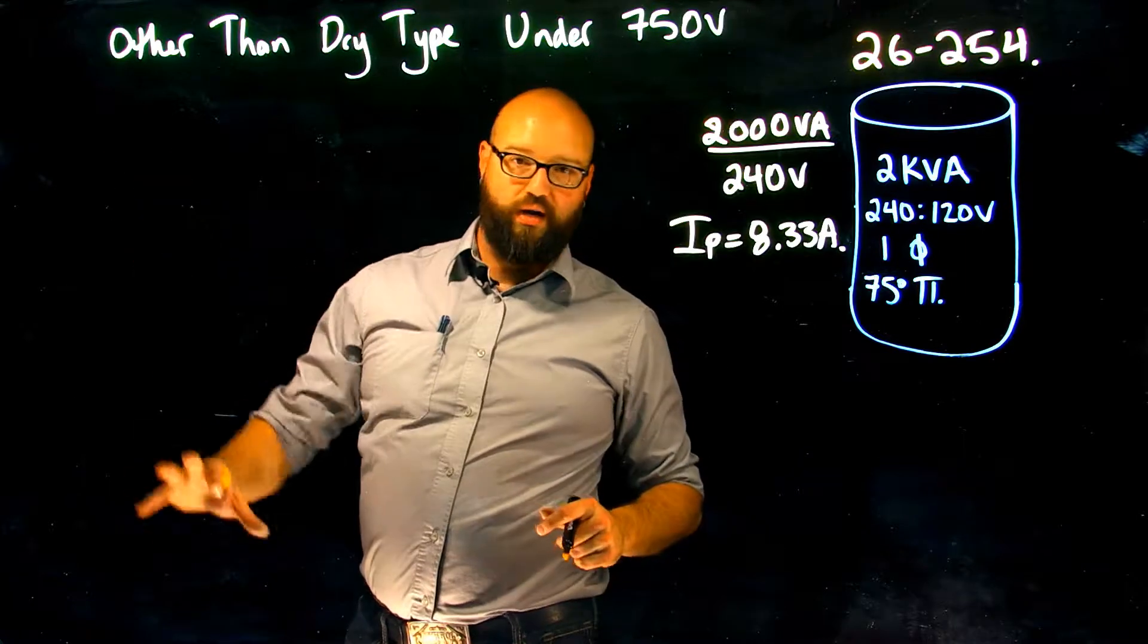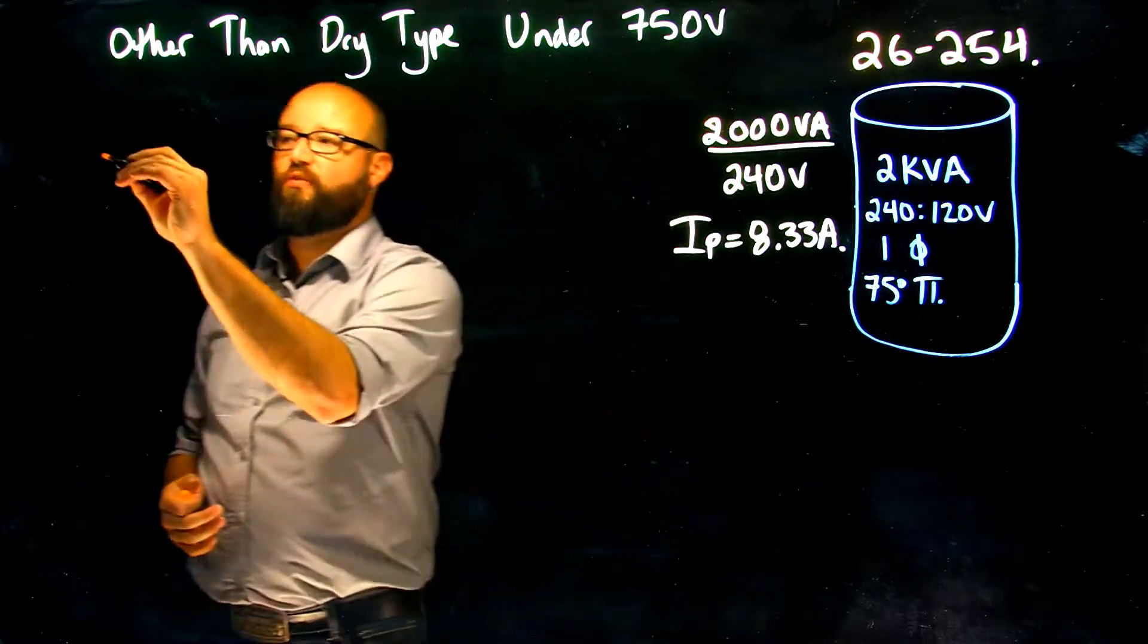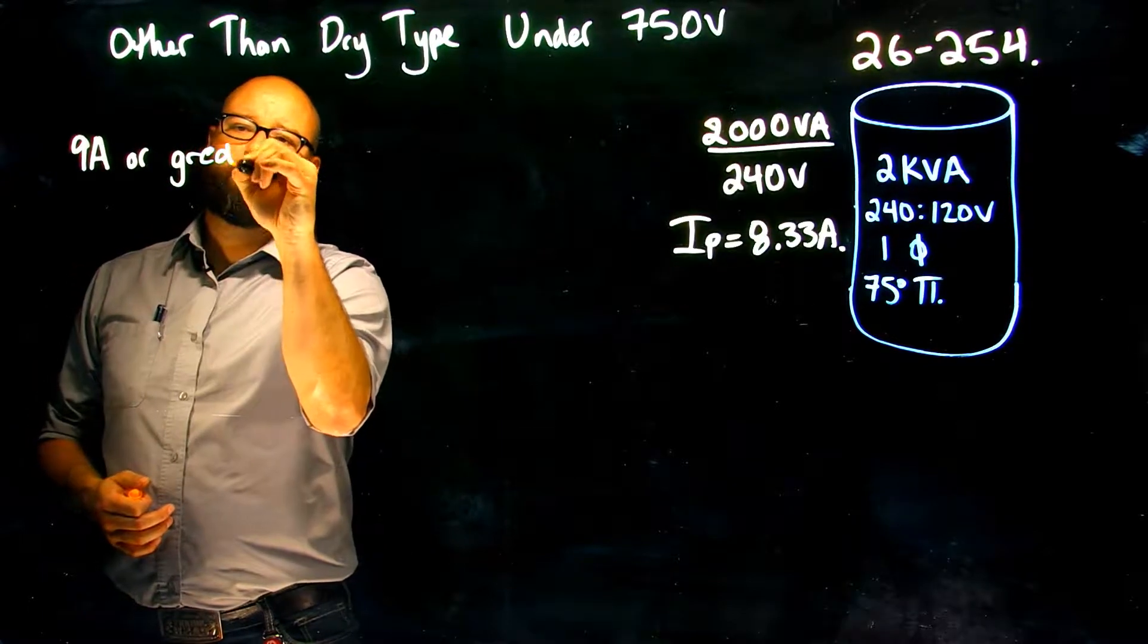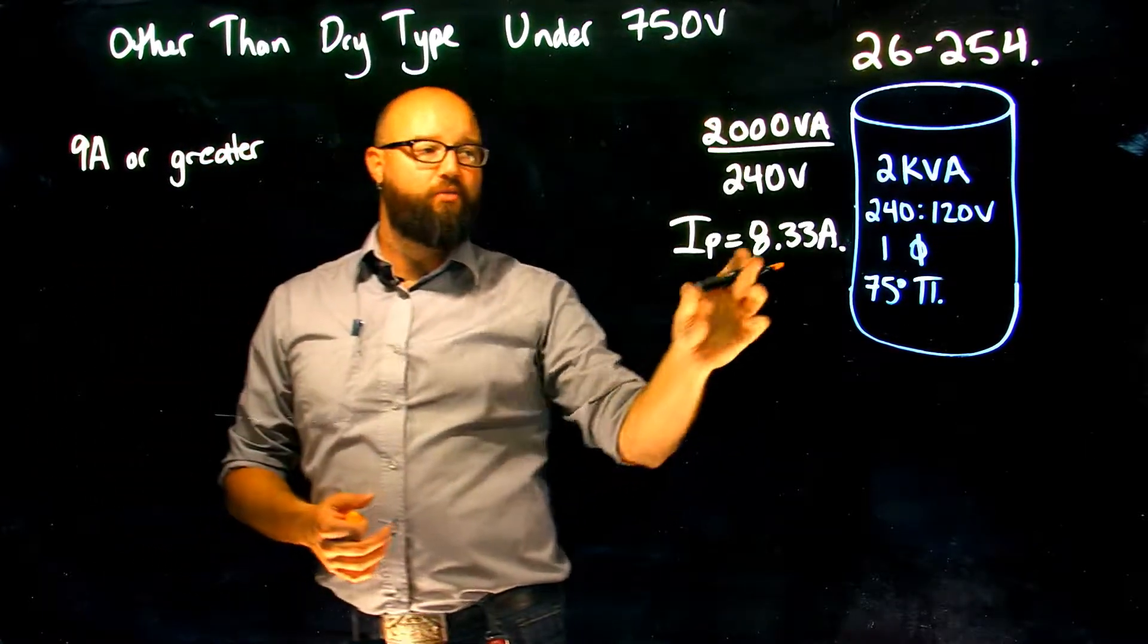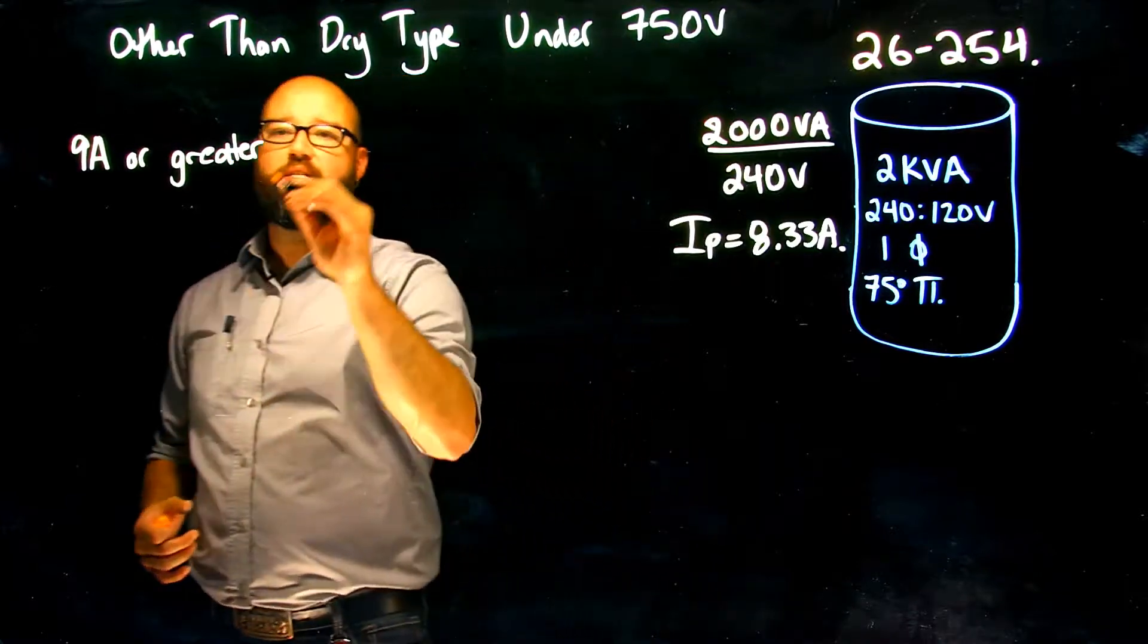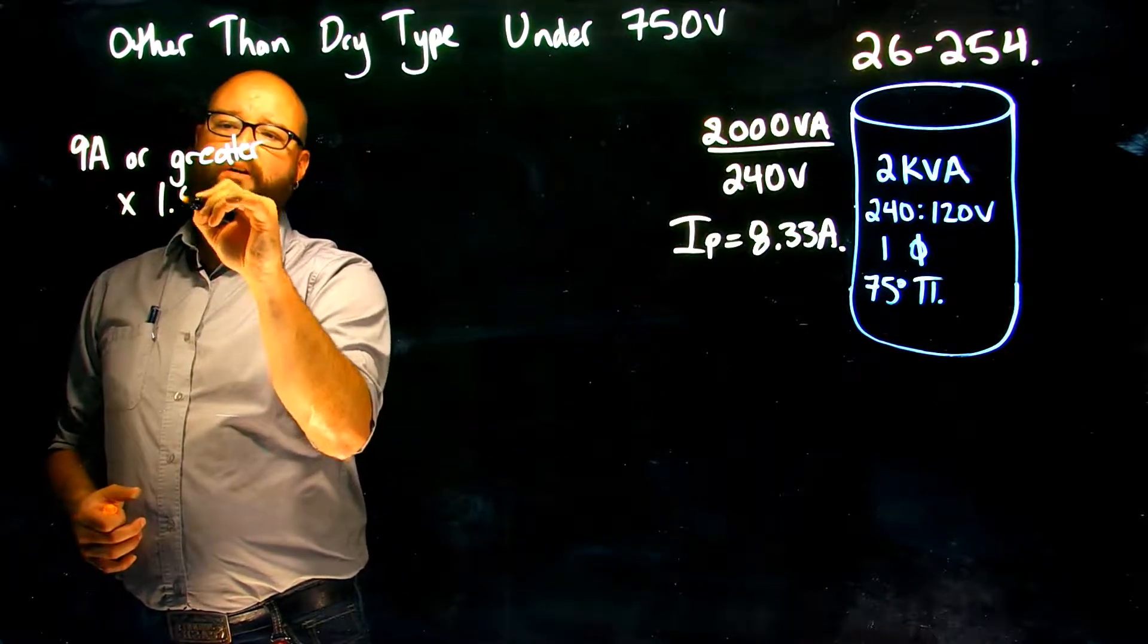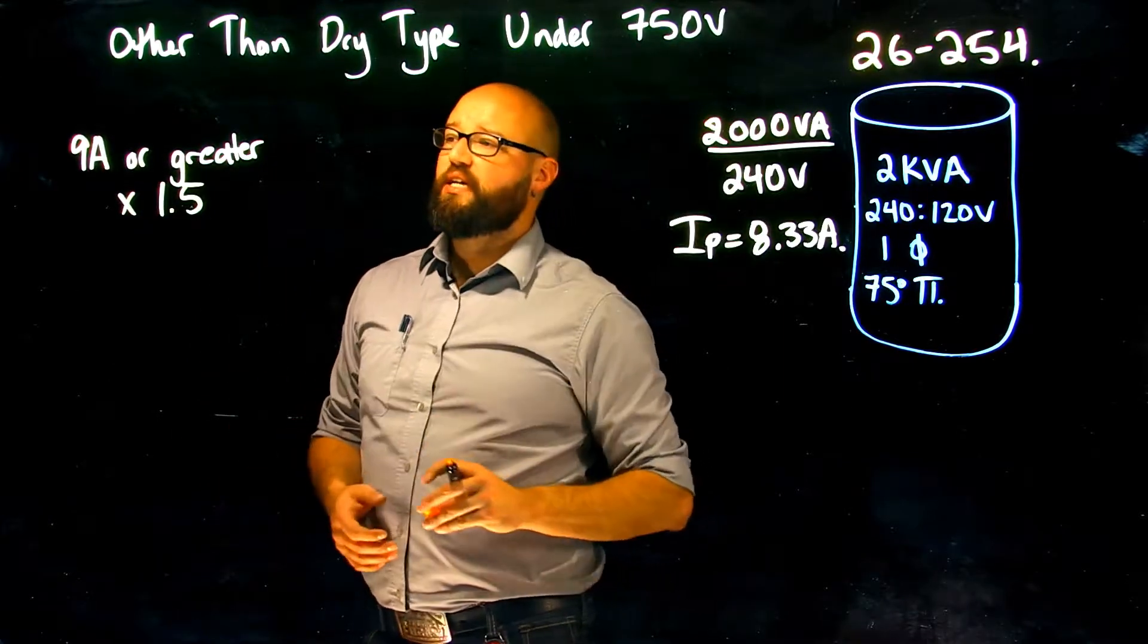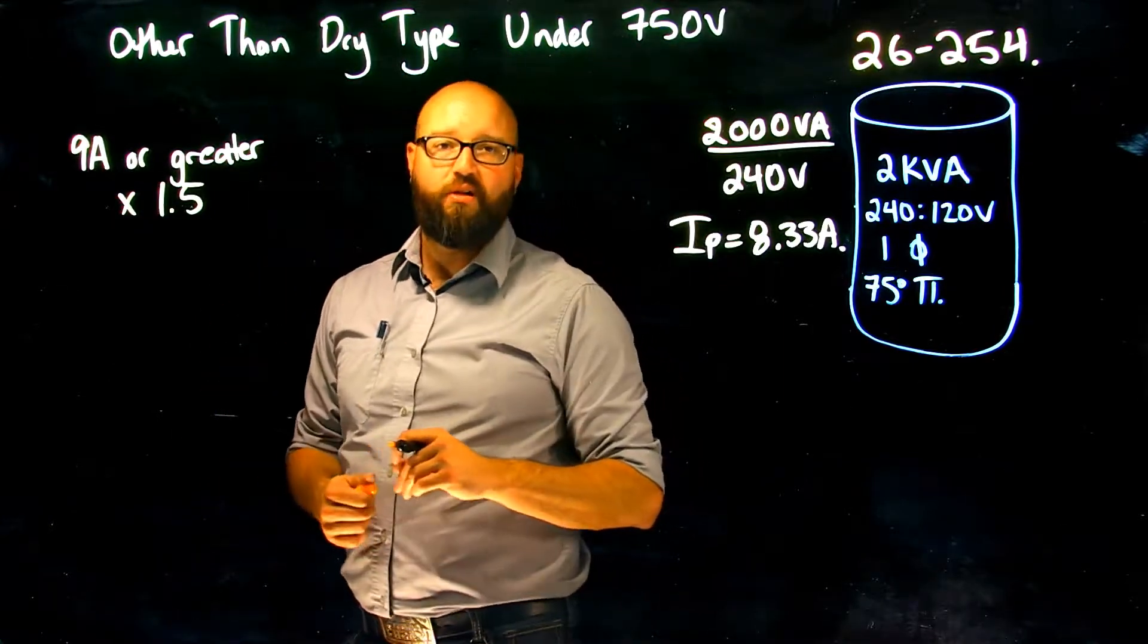So if we have 9 amps or greater, if my primary rated current is greater than 9 amps, it tells me my multiplier is 150 or 1.5.